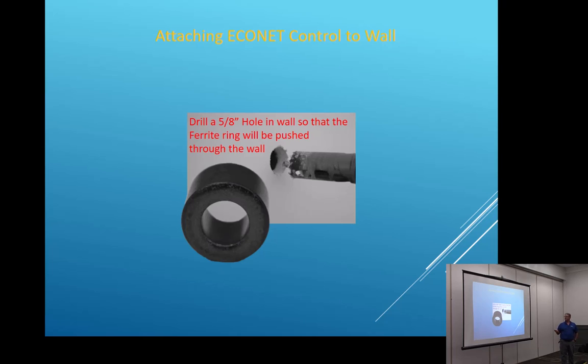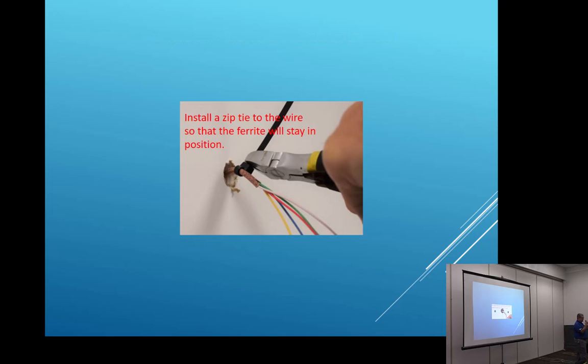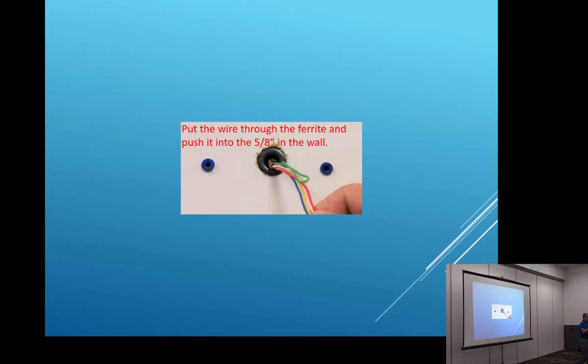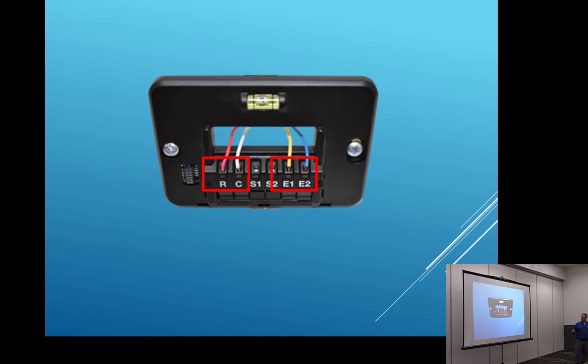And if there's any kind of line noise or anything, because this is communicating, this is data, this is pulsating information going through there, it drowns out any of those electrical noises, okay? If you don't put this in there, you could have erroneous communication errors, and you don't know what it is. It could be because this little donut isn't back there behind that thermostat in the wall, okay? It doesn't have to be perfectly mounted like that in that perfect little hole. It's not going to hurt, okay? You still want to make sure you seal up this hole so you're not getting air infiltration from the back side of that, right? So you don't want a gargantuan hole, but if you do, you need to seal it up, okay?